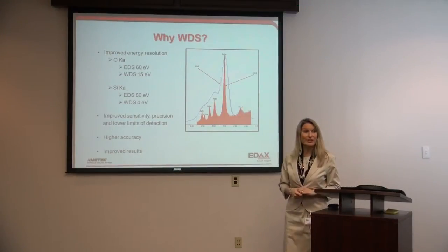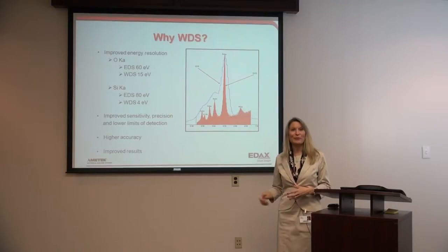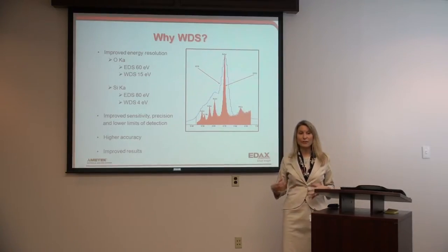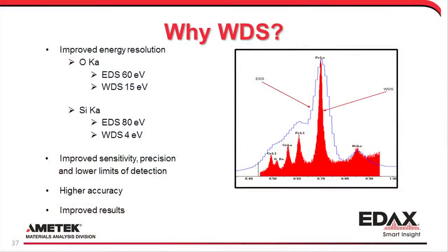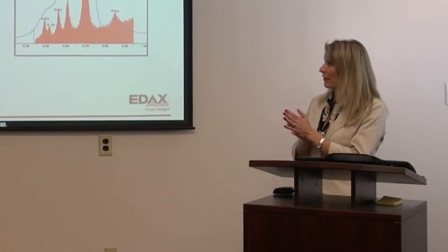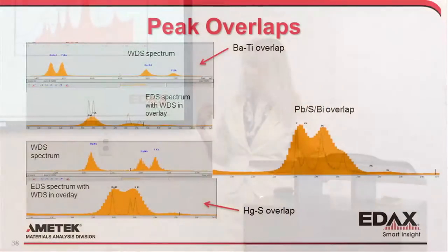Now moving along to WDS. So with all of that capability, why would we need WDS? WDS is taking the EDS analysis even further. In areas where we have overlapping peaks, so larger, broader resolution, we're able to get finer analysis and better resolved peaks. Those better resolution peaks give the better ability to detect low limits of detection because they're separating out the counts where they belong to the elements that they belong to, better accuracy and improved results.